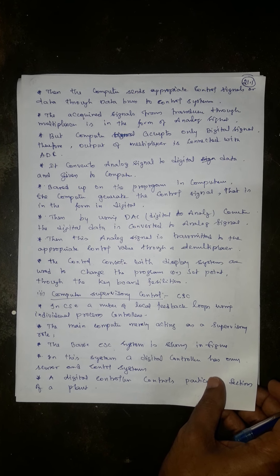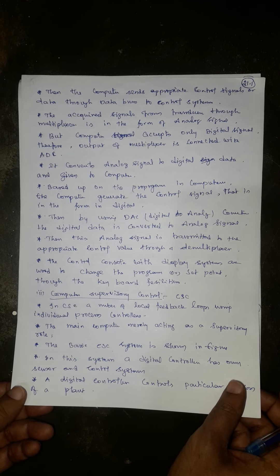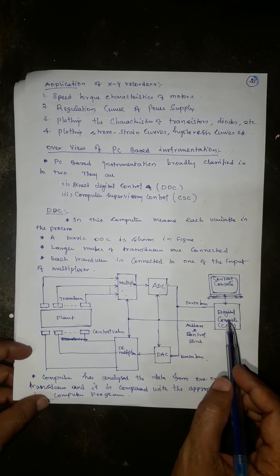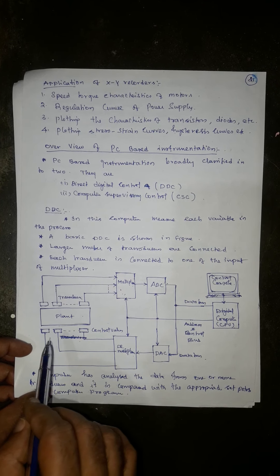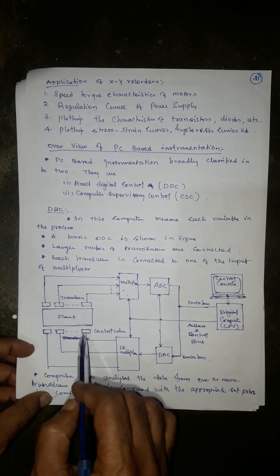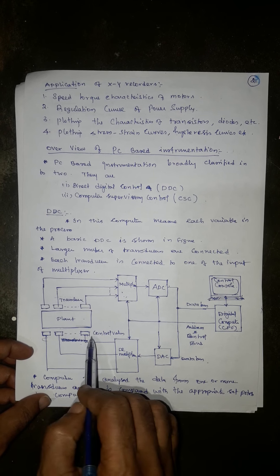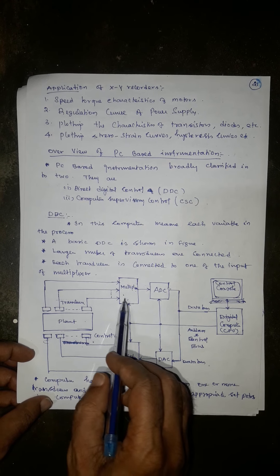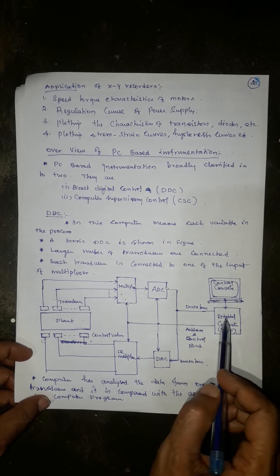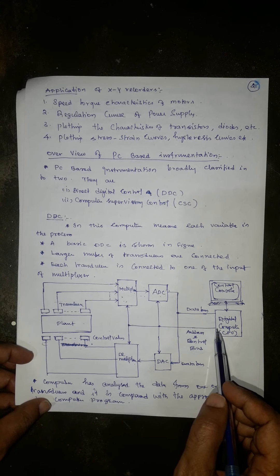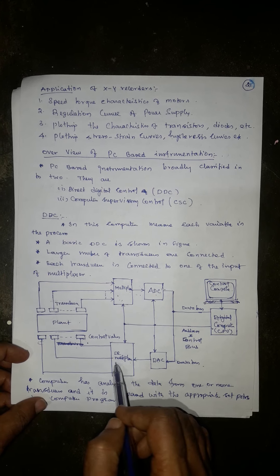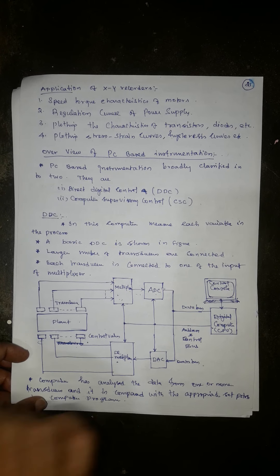The control console with a display system is used to change the program or set point through a keyboard. Any number of transducers or control valves can be programmed through the digital computer console. In the block diagram: the transducer feeds into the multiplexer; the analog output is converted to digital and given to the computer; the computer generates a digital control signal; that digital data is converted back to analog and given to the demultiplexer; and the final control element operates in analog form.